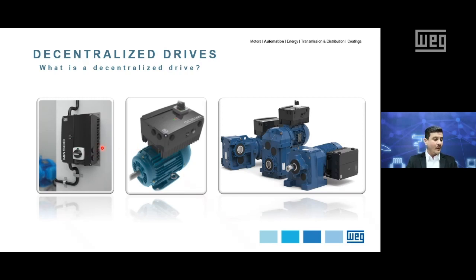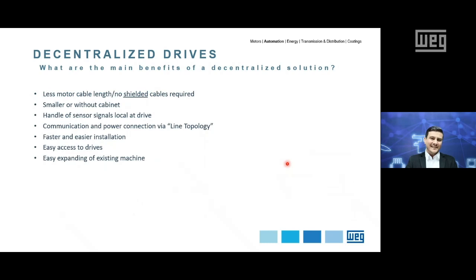Here we have one example where the VFD is mounted against the wall, but at the same time near the motor set. Here we have a VSD coupled directly to the motor terminals. And here we have a complete set composed of a gear unit, motor, plus the VSD. So what are the main benefits of a decentralized solution? We can start with fewer motor cables and no shielded cables required. Since the VSD is now installed on the motor terminals or close to the machines, the output cables are shorter. And here we begin to see potential saving possibilities, considering the high cost of the shielded cables between the drive and the motor.